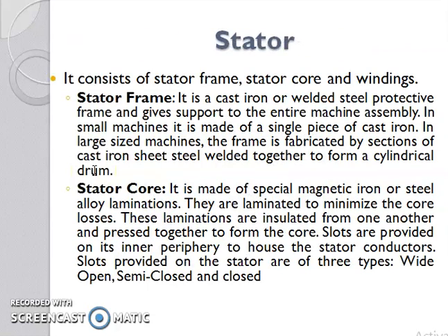See, the stator consists of the stator frame, stator core, and stator winding. As already discussed, the stator frame is made up of cast iron or welded steel protective frame, which gives support to the entire machine assembly. Especially in the case of small machines, it is made up of a single piece of cast iron material. But in the case of large size machines, the same frame is fabricated using sections of cast iron or steel sheets welded together to form a cylindrical drum.